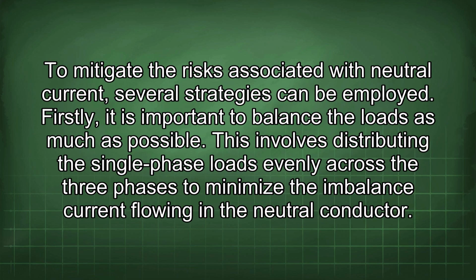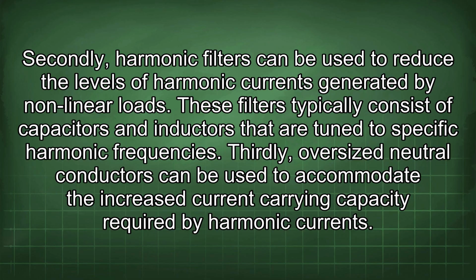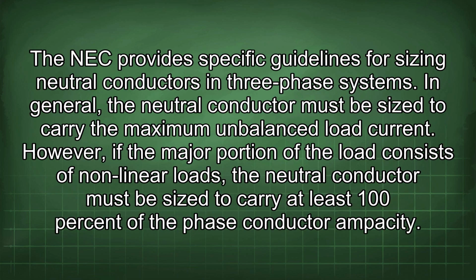To mitigate the risks associated with neutral current, several strategies can be employed. Firstly, it is important to balance the loads as much as possible. This involves distributing the single-phase loads evenly across the three phases to minimize the imbalance current flowing in the neutral conductor. Secondly, harmonic filters can be used to reduce the levels of harmonic currents generated by nonlinear loads. These filters typically consist of capacitors and inductors that are tuned to specific harmonic frequencies. Thirdly, oversized neutral conductors can be used to accommodate the increased current carrying capacity required by harmonic currents. The NEC provides specific guidelines for sizing neutral conductors in three-phase systems.